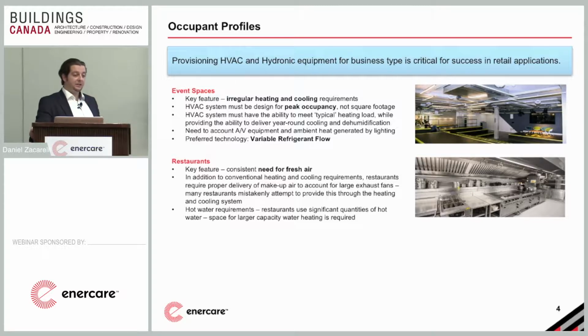So it's not just your tenants that are uncomfortable, you're sucking out all the heating and cooling that your rooftop unit's putting in there. Tenants are hot, cold, uncomfortable, doors are difficult to open, but also your equipment, even things like gas-fired stoves, for example. You're degrading the life of the equipment, increasing costs for breakdown, and maintenance is required at a much higher level. And if you don't provision for a makeup air unit, your other option is very expensive equipment that does not need that, like sealed combustion, for example.